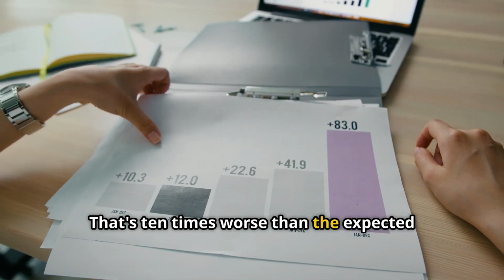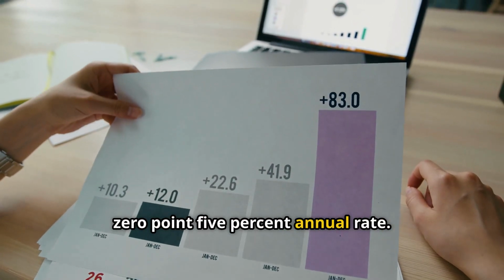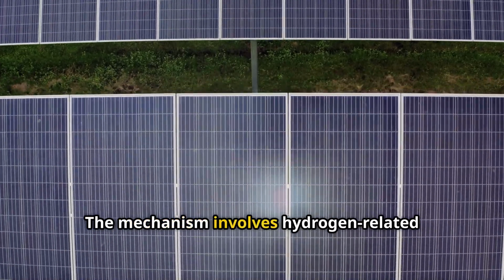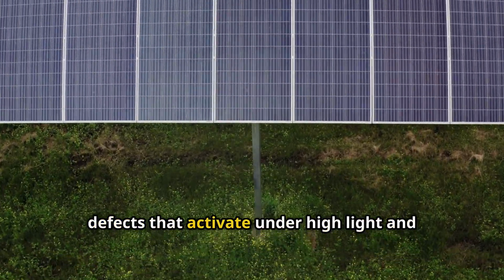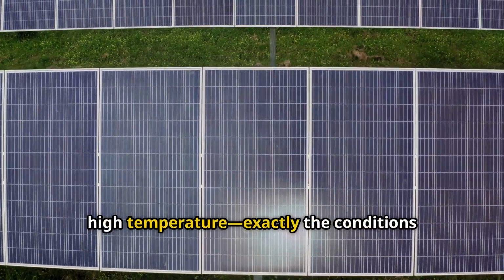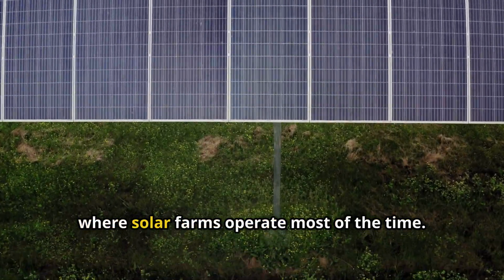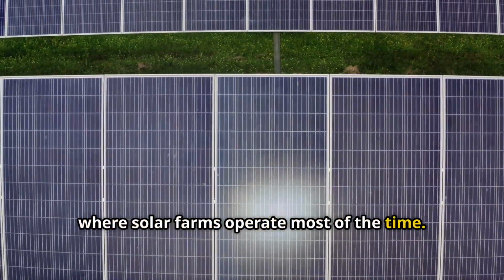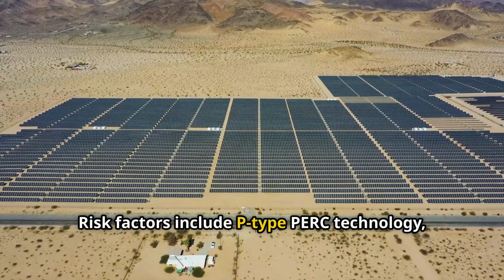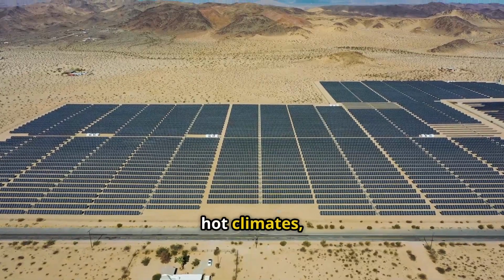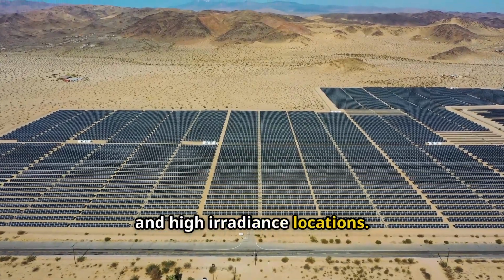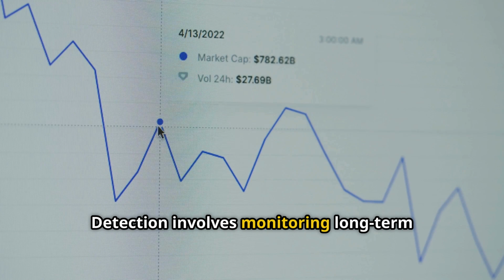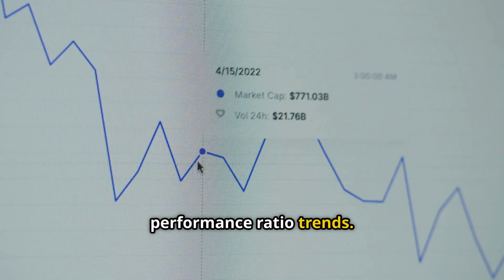That's 10 times worse than the expected 0.5% annual rate. The mechanism involves hydrogen-related defects that activate under high light and high temperature, exactly the conditions where solar farms operate most of the time. Risk factors include P-type PERC technology, hot climates, and high irradiance locations. Detection involves monitoring long-term performance ratio trends.